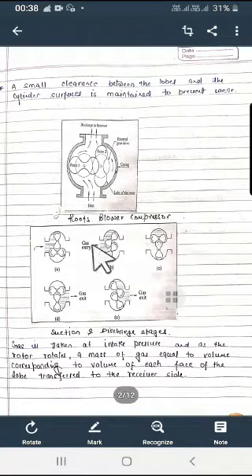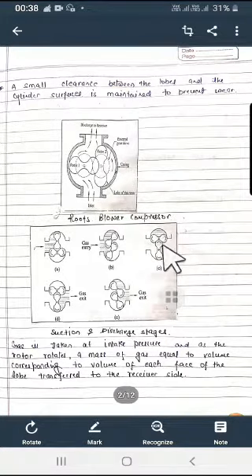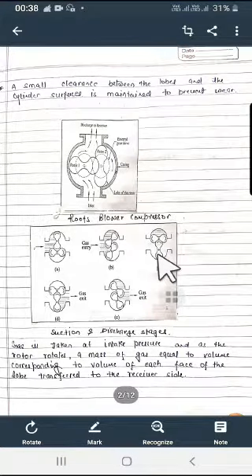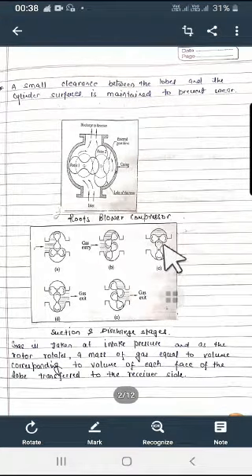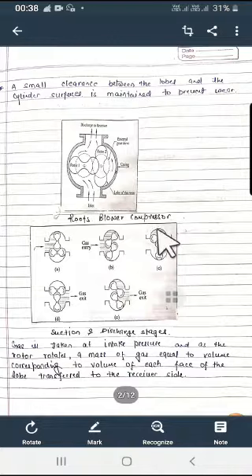Now what will happen in the next stage? With the further movement of the first rotor as it moves in clockwise direction, second rotor rotates in the anticlockwise direction. At this stage some high pressure gas will rush back from the receiver and it mixes with the volume of air until the pressure is equalized.